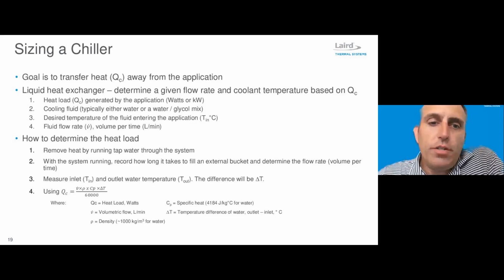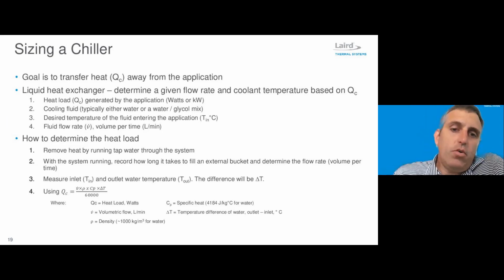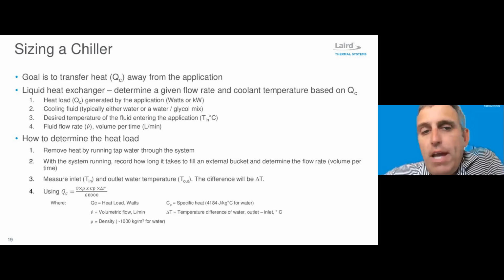So real quickly, I just want to talk a little bit about what it takes to size a chiller. The whole goal is to take heat away from the application. In order to do this, there's a heat exchanger, in the example I had shown of the laser, that's been designed under specific conditions in order to function properly. With a certain heat input, the heat exchanger will need a certain flow and temperature in order to transfer that heat.